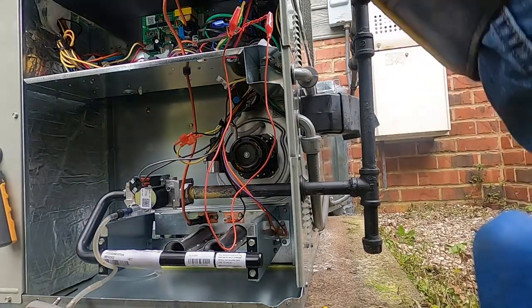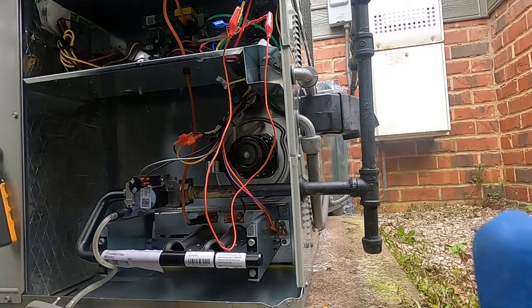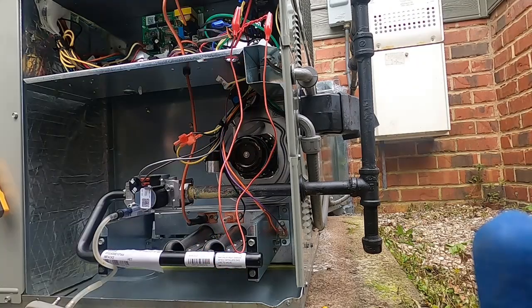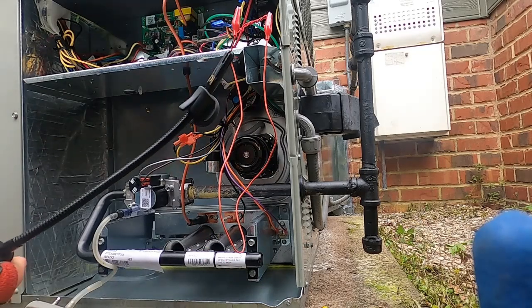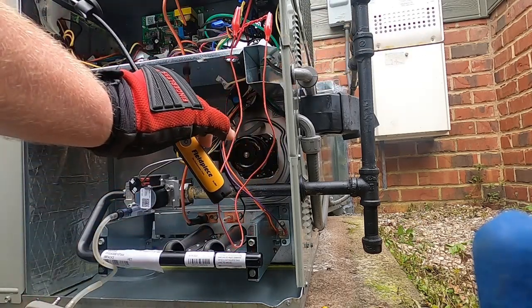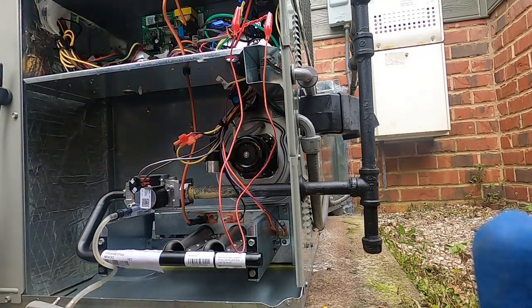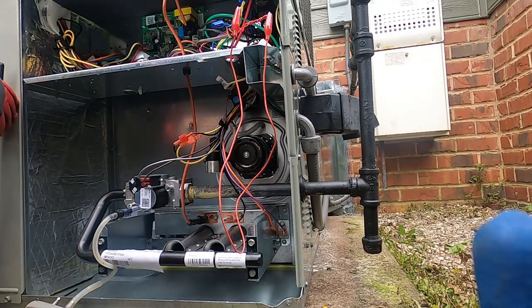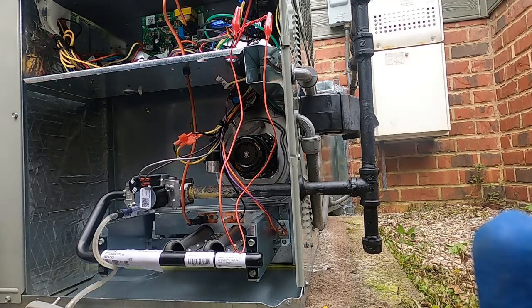Turn the gas back on. So, got my probe here. Just going ahead and give this information. I'll need it. Want to check my refrigerant charge, outdoor wet bulb about 55 degrees. Humidity's 51. Outdoor dry bulb 64. Take a screenshot of that, because I'll need that information to fill in some blanks on my paperwork.